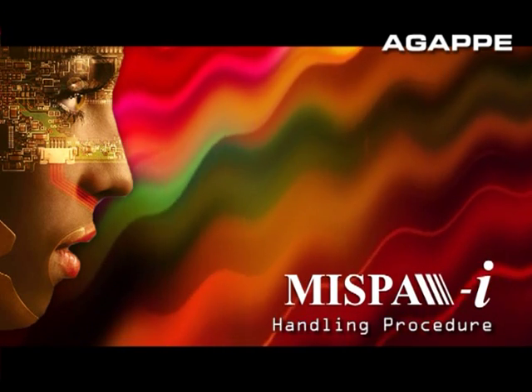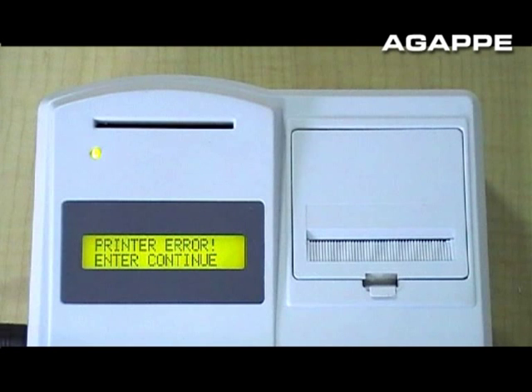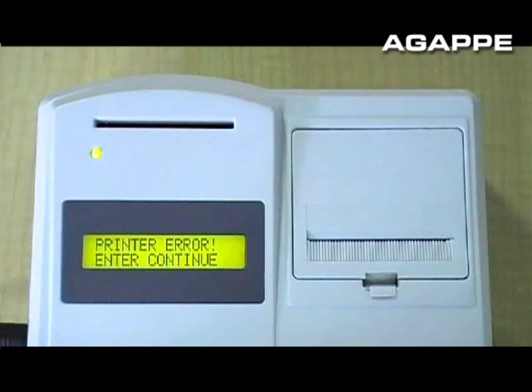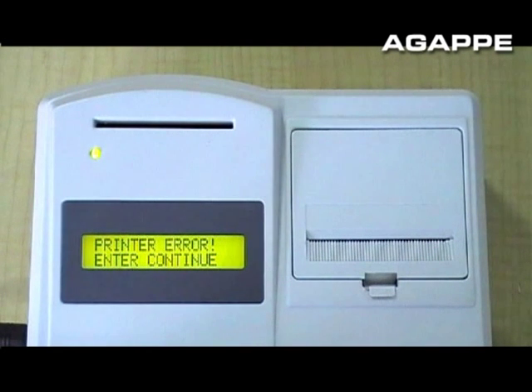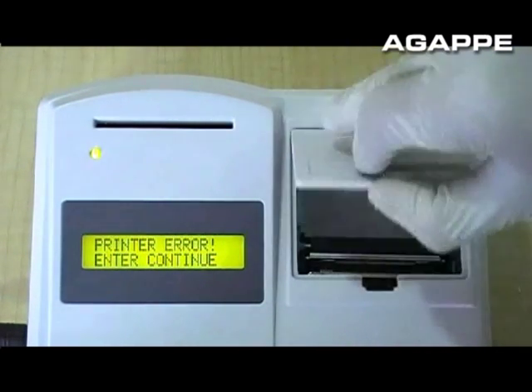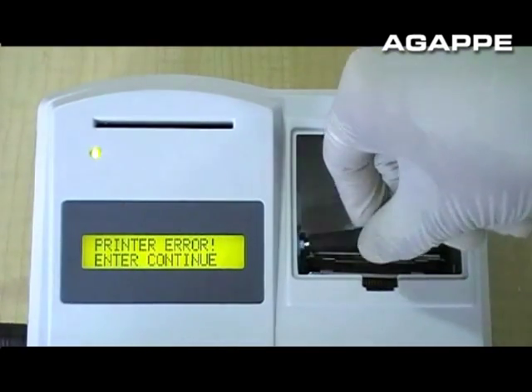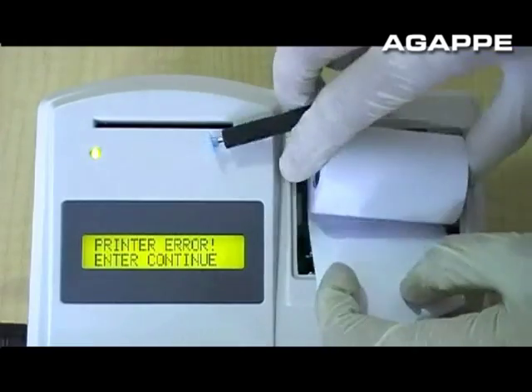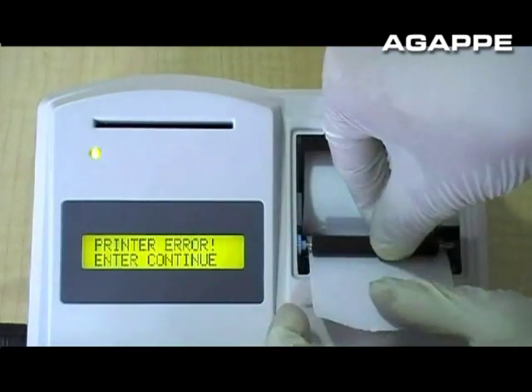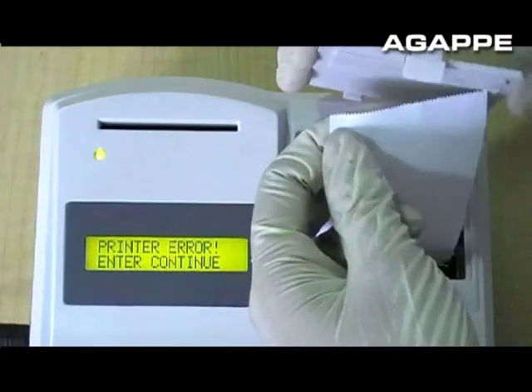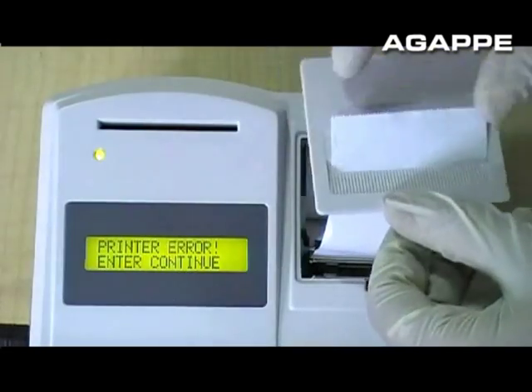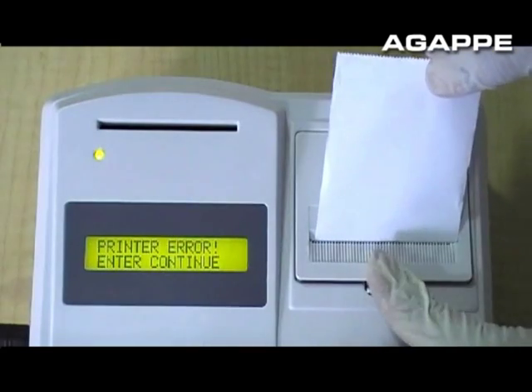Handling procedure. If the equipment is out of printer paper, it will prompt you with a warning message. You can continue the test if you want to by pressing the Enter key, but the equipment will hang up after this test. You have to reload the paper roll whenever the printer error shows on display. We will show you how to do this. Please follow the procedure. First, remove the printer lid. Then carefully remove the pinch roller. Put the new refill roll into the paper tray. Put the pinch roller back by gently pressing it. Pull the paper through the slit in the lid and put it back in place.